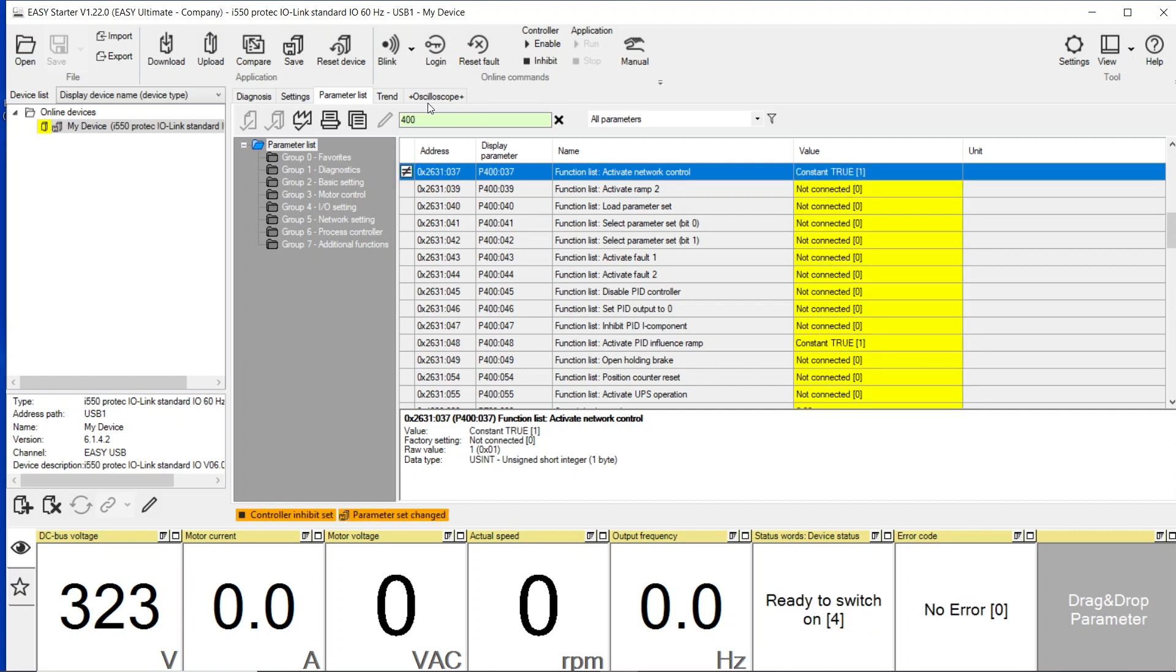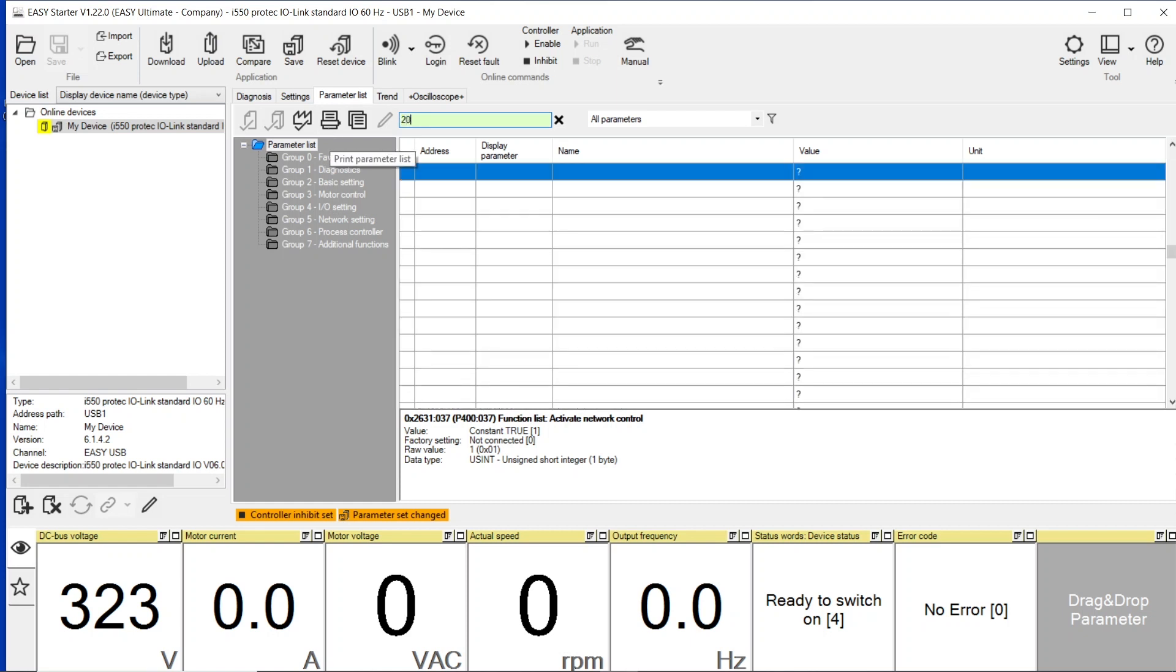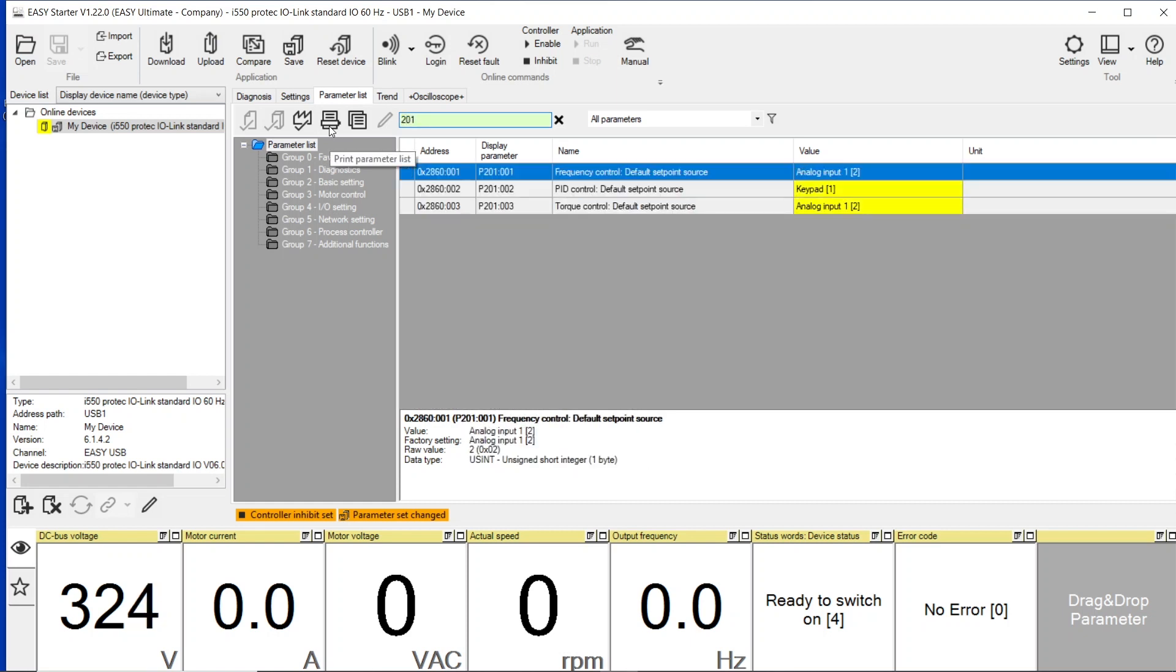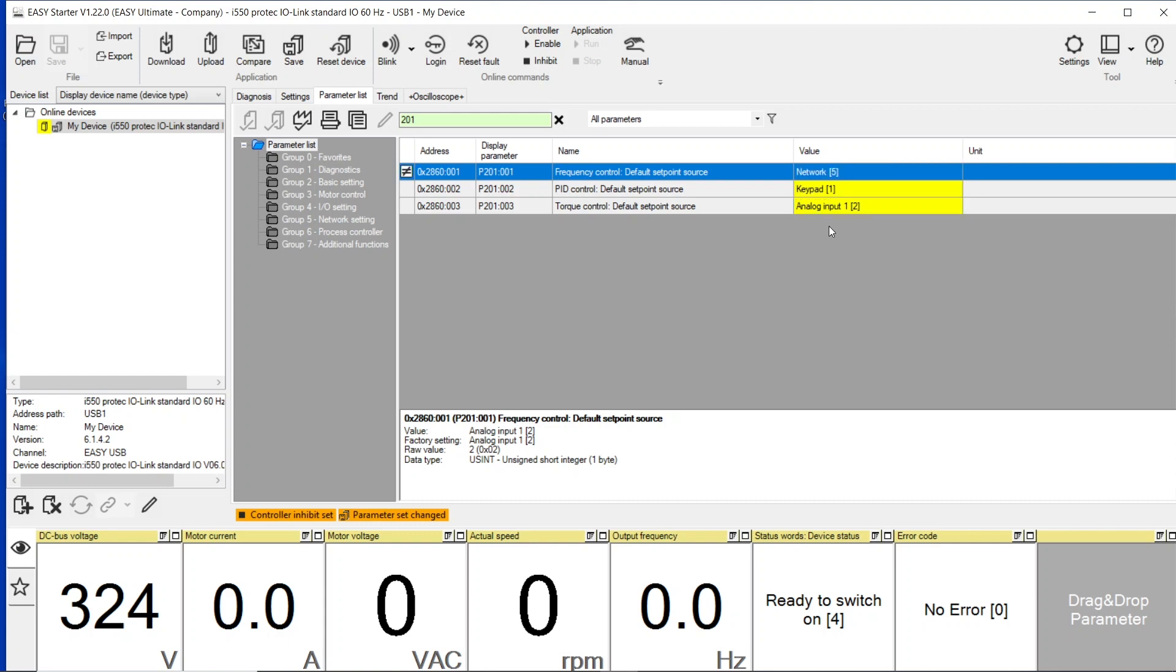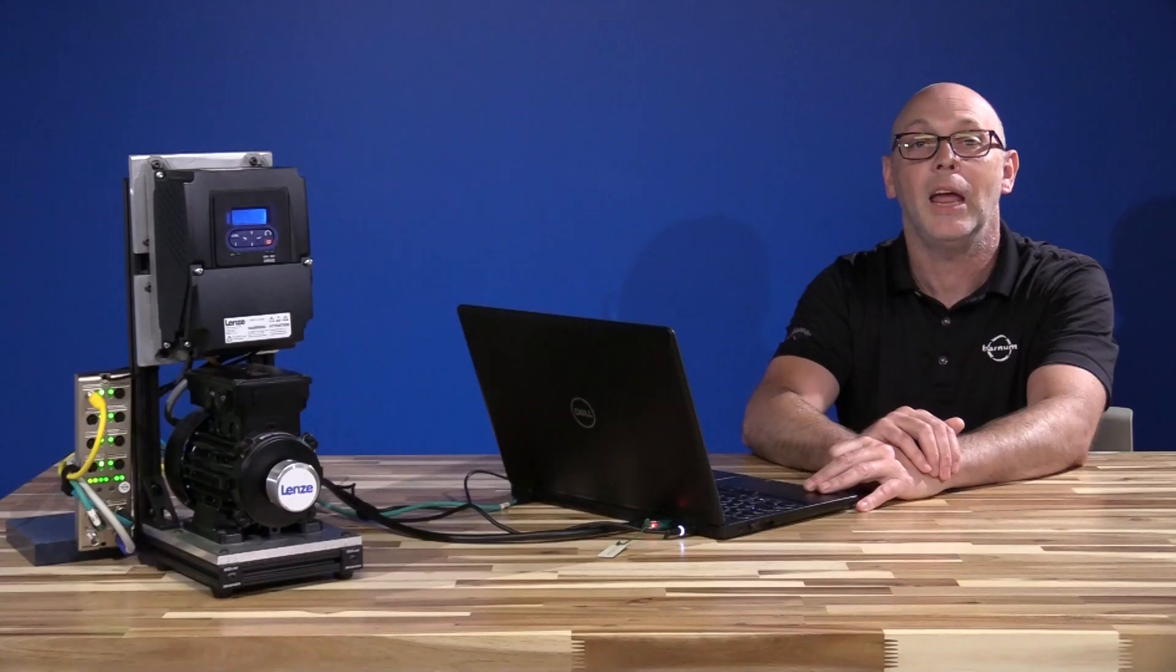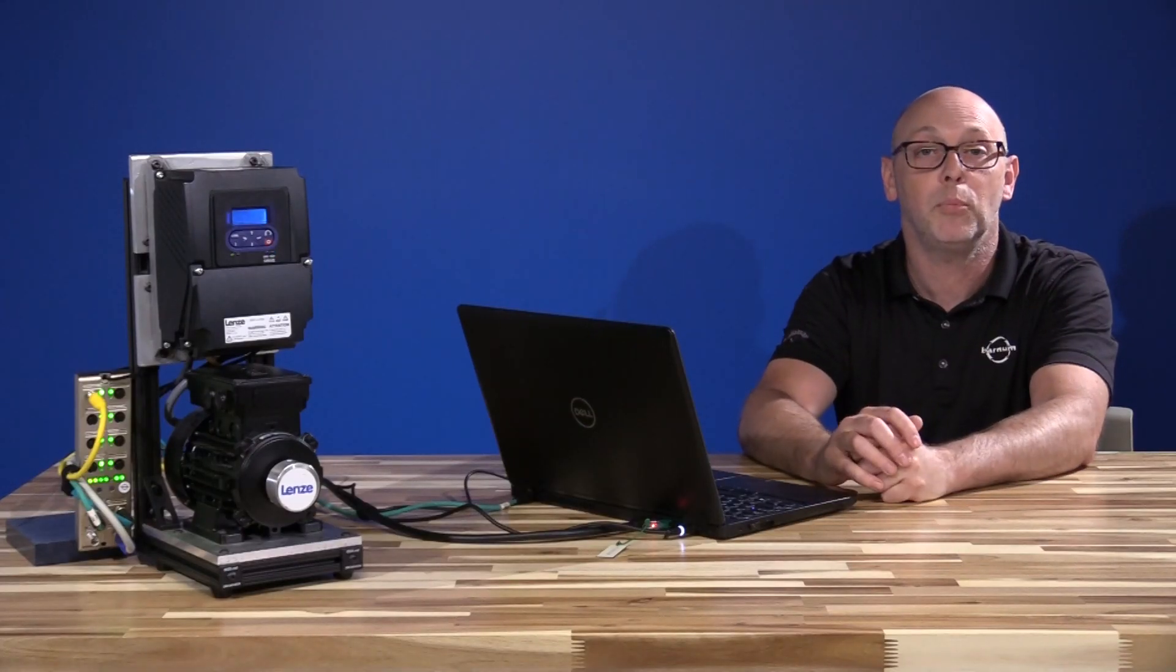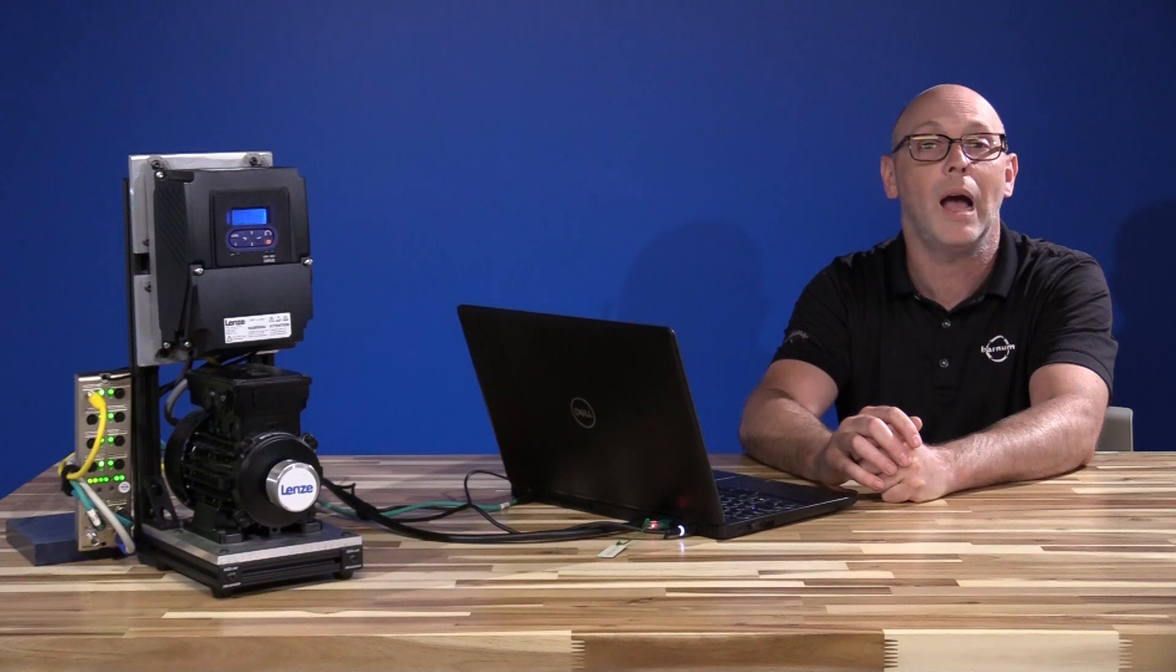The second parameter we need is under parameter 201. We're going to change the frequency control. This is actually what controls the speed from an analog input. We're going to switch that over to Network, which is number five. Once both of these parameters are set, we're going to press the Save button. And your i550 protec is ready for IO-Link.